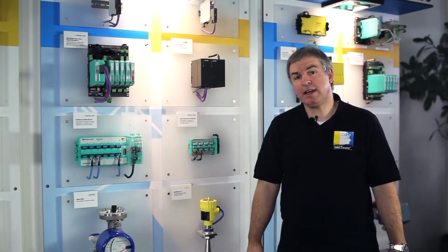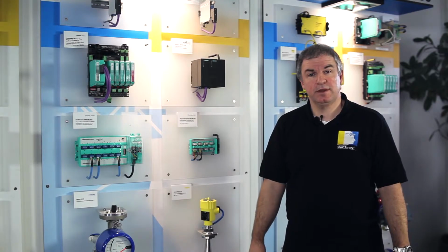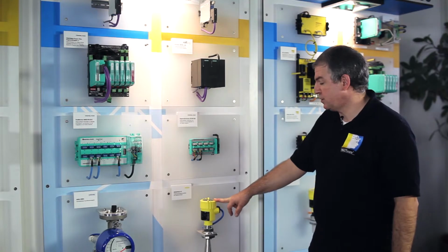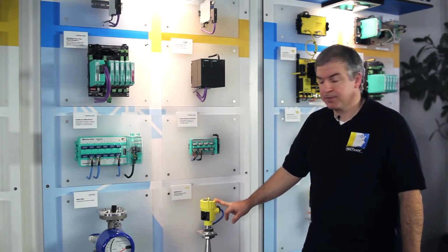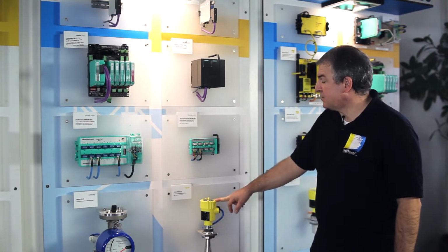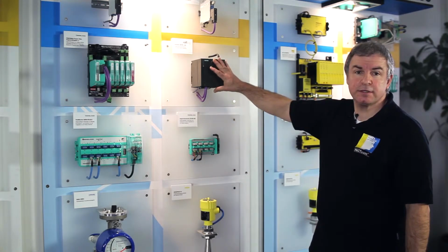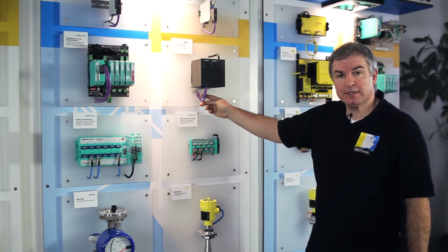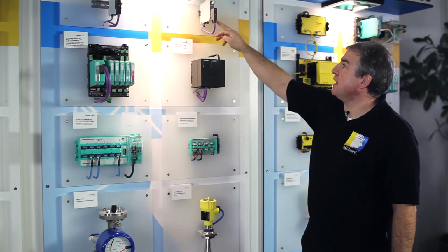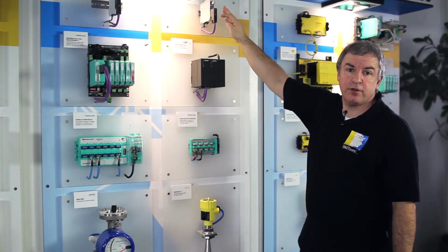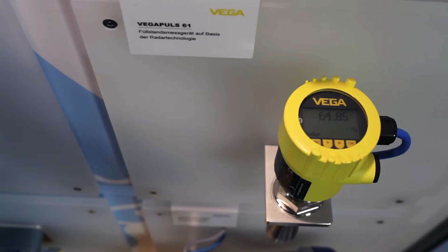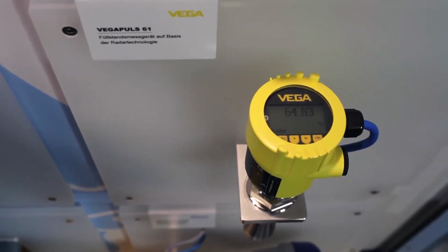Nowadays, many plants are networked via bus systems. I would like to show you how easy it is to have access to this Profibus PA sensor. The radar level sensor is connected to a Profibus segment coupler, which is running Profibus DP, which is then connected to the Ethernet network by using a gateway. The PC is connected on Ethernet. That means with PACTware you have easy and complete access to your sensor.